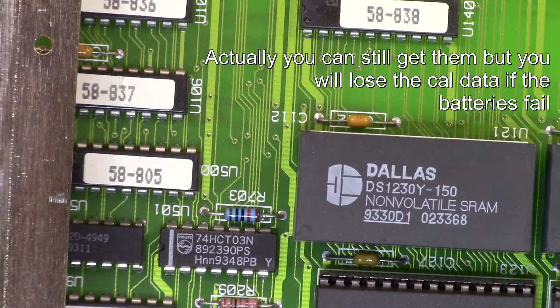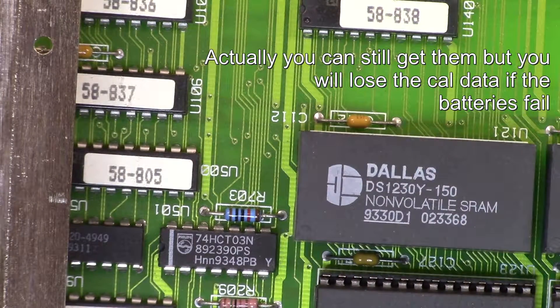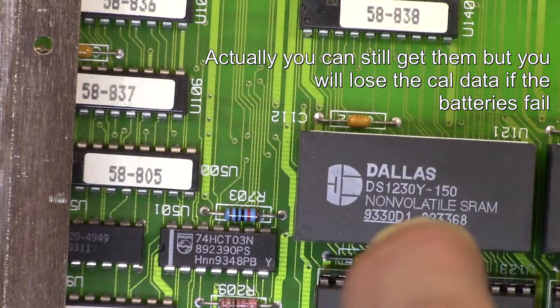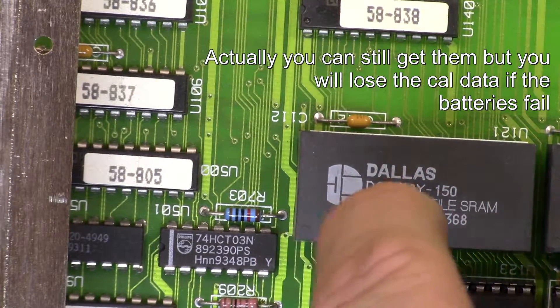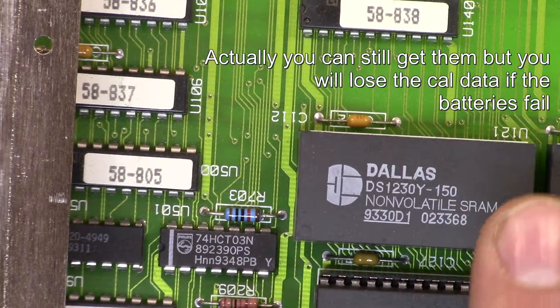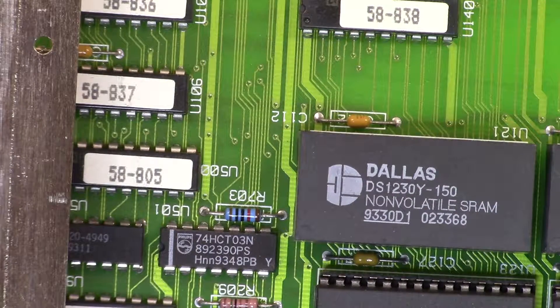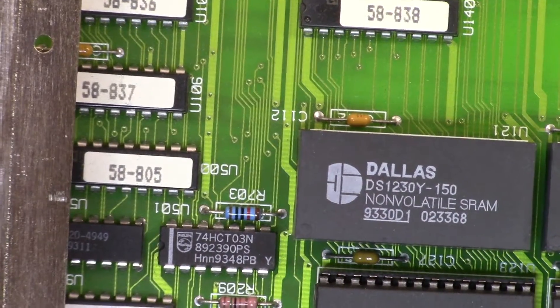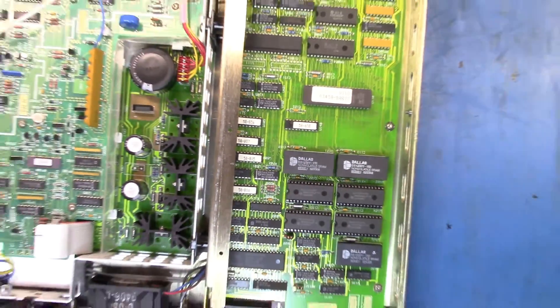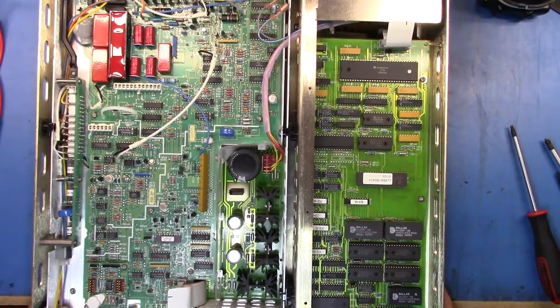So I want to send it away for a manufacturer calibration primarily to get those items updated. My understanding is that when the manufacturer does the calibration, they will also update these batteries. Because these are mounted on the board, they'll either replace the board or replace these units — I need to go check that. But that certainly looks like what I have on here.